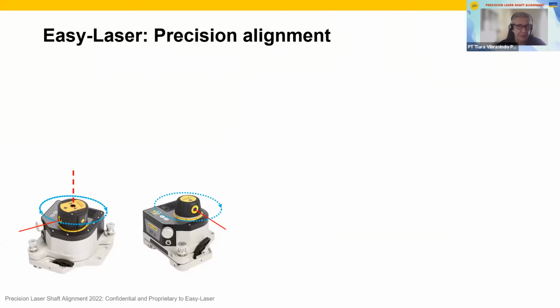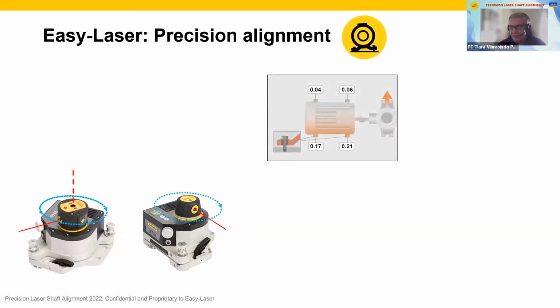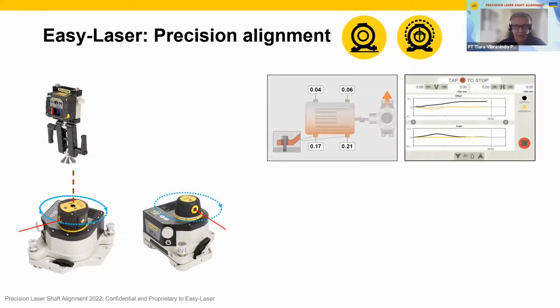Such systems offer today many more functions and operations for measurements. So measuring the machine software is included by default, of course. The same applies to monitoring the machine through dynamic stresses at the machine with special brackets. So here we're having thermal growth. We have soft foot. There's the special bracket that allows you to use the same measurement laser and detector measurement units, not installed on the shaft, installed on the body of the machine, to measure dynamic stresses.